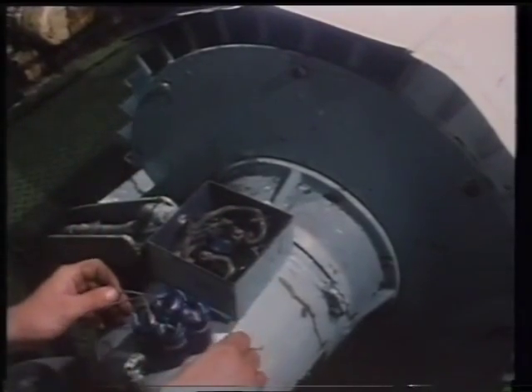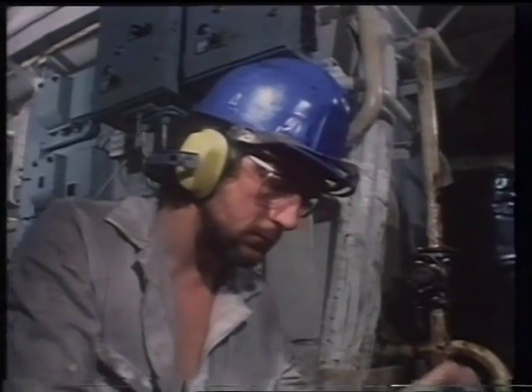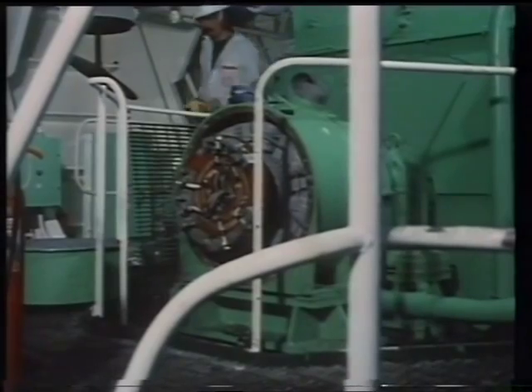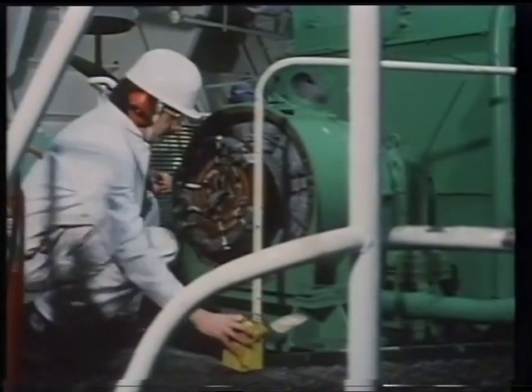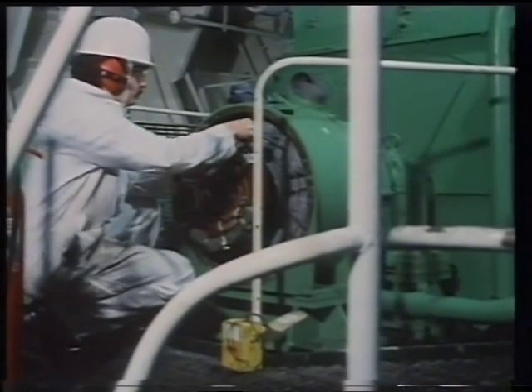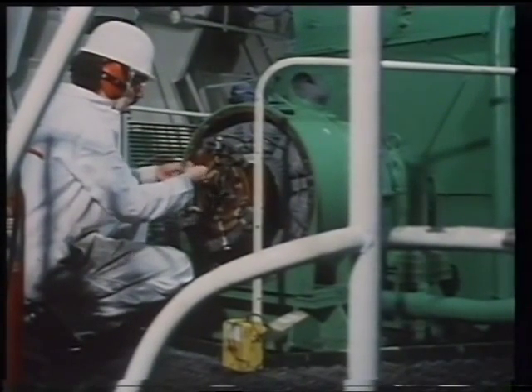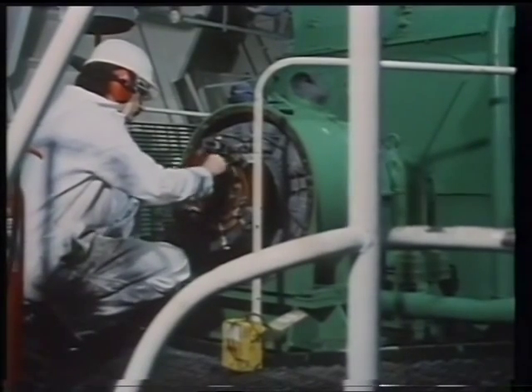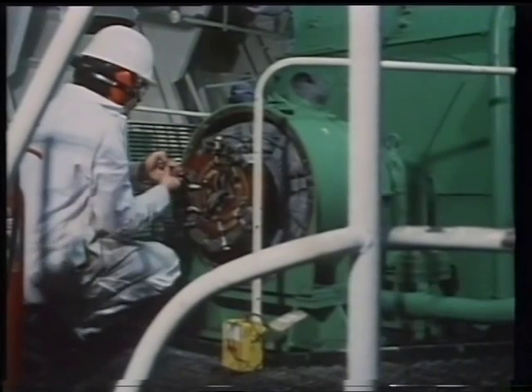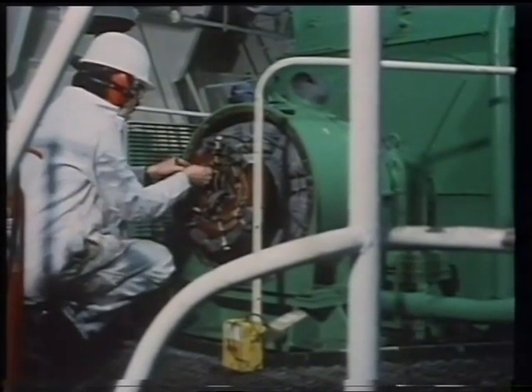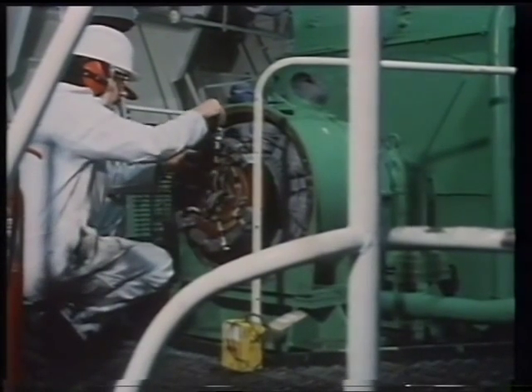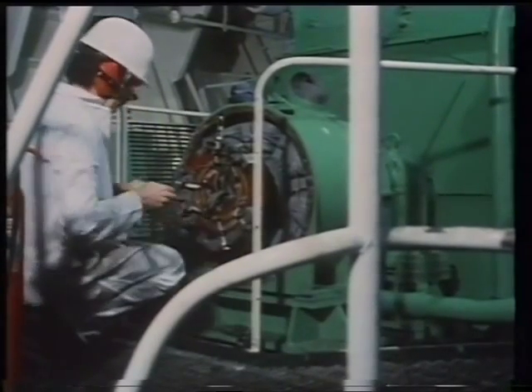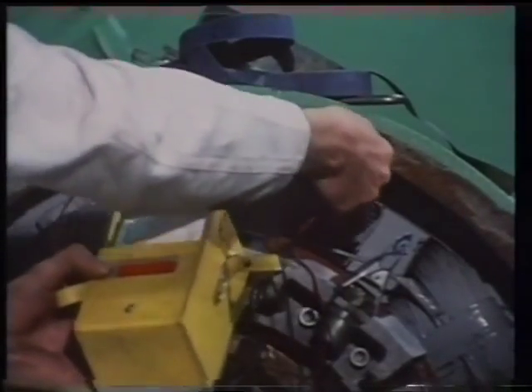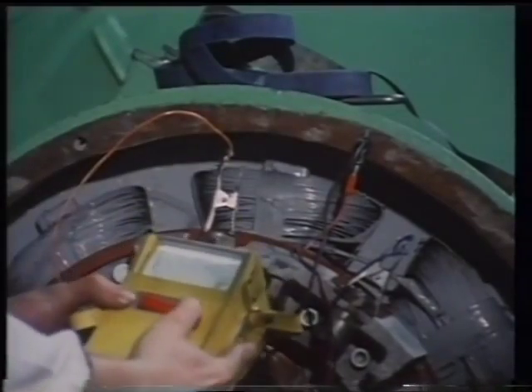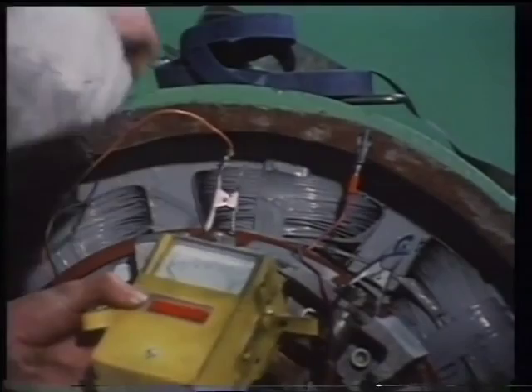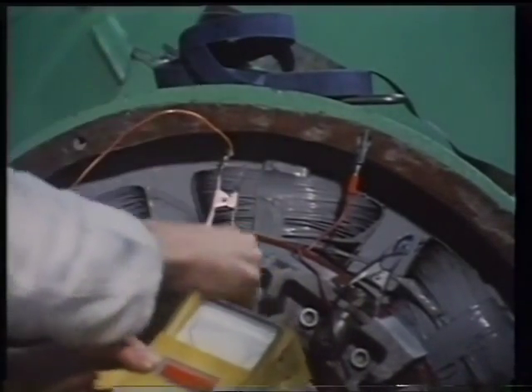If this procedure does not produce the required result, shut down the prime mover and lock off its controls. If the need arises for further tests, an important point must be kept in mind. An insulation tester must not be used on an electrical circuit which incorporates electronic components such as diodes. These must be shorted out before any insulation resistance readings are taken. Here, the field coils are tested to earth. Note the correct procedure being followed. First, the tester is checked, then 2 good earth points established, then the actual tests are made.